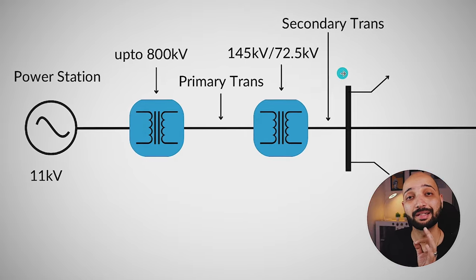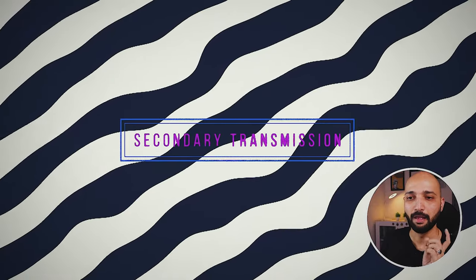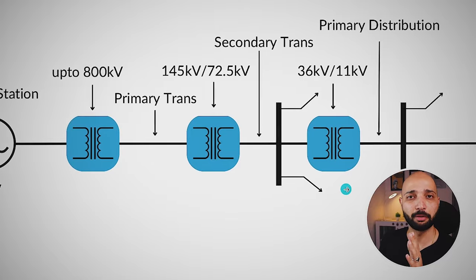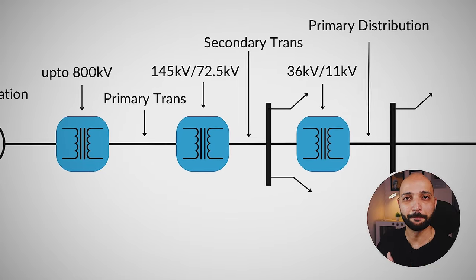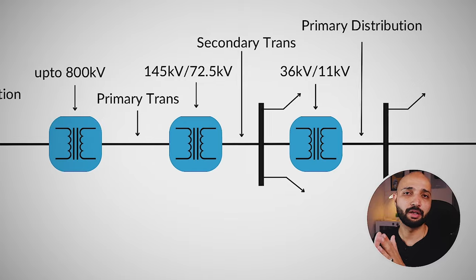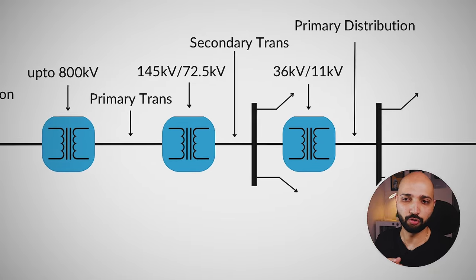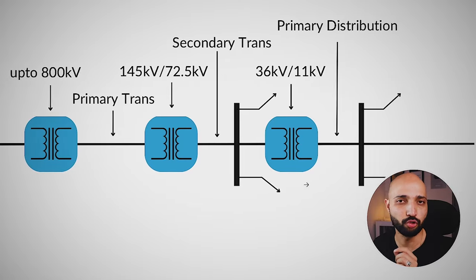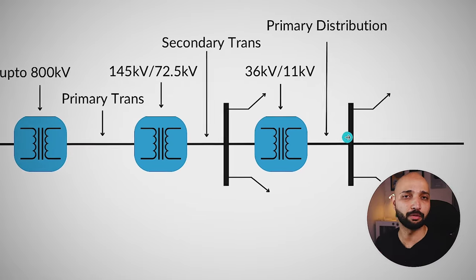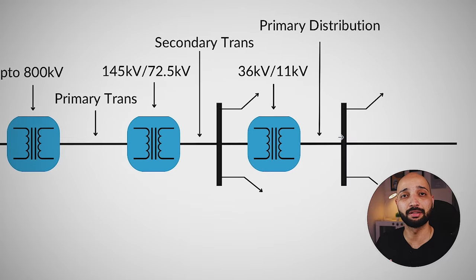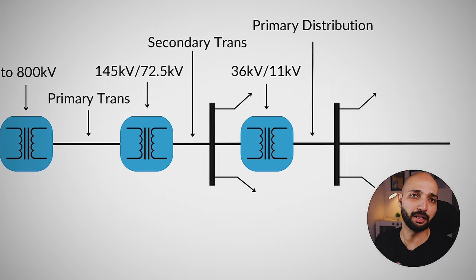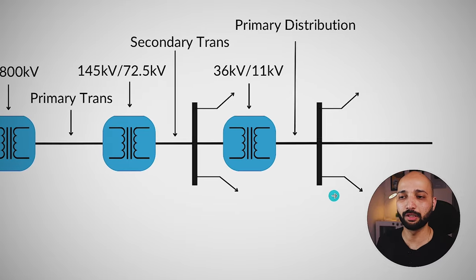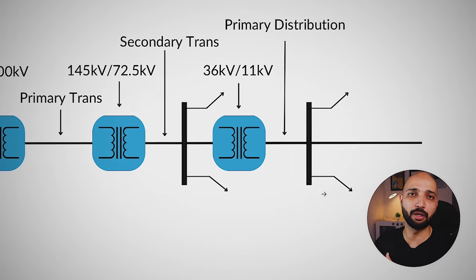This phase is what we call secondary transmission. After secondary transmission, the power is again stepped down to 36kV or 11kV, and we enter the distribution zone. This 36kV or 11kV level is what we call primary distribution. From here, power can also be given to consumers who need 36kV or 11kV directly in their plant.